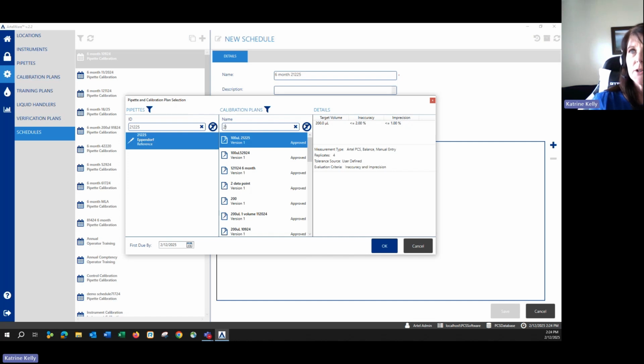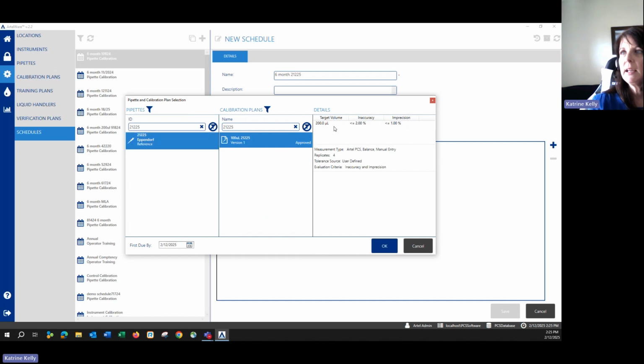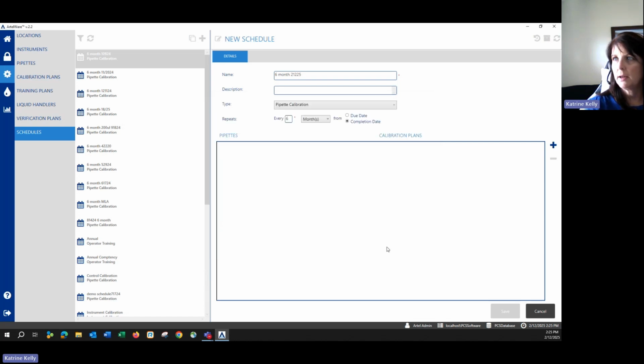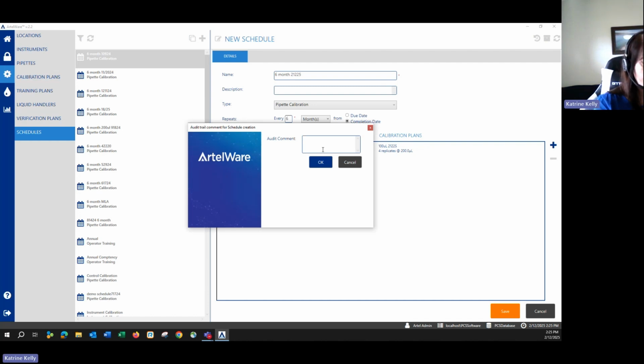So you're not sorting through a bunch, you can filter. So there's my pipette, there's my plan, my target volume is 200, my inaccuracy is 2%, my imprecision is 1%. I can change the first due date. If it's not due until the end of the month, I can put that in there and then click OK. Did not add it. Oh, there it is. You can add more than one pipette to the schedule. You can also add multiple pipettes at one time as long as the pipettes are all of the same volume. And then enter in an audit comment and then click OK.